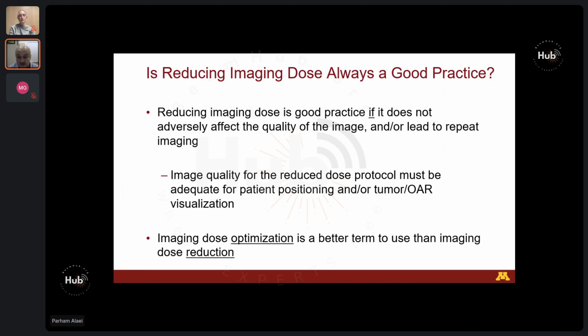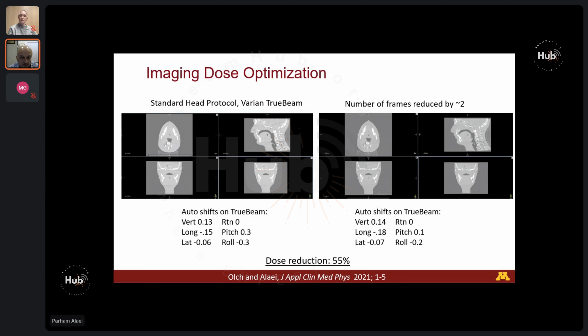We gradually reduced the frames per second, or the number of frames, or the mAs, maybe kV on the head and neck, and then we did the auto match feature on the TrueBeam in the LINAC. So we were just checking to make sure the auto match based on bony anatomy works with the lower dose protocol. Again, there is no soft tissue contrast in here, it's a phantom, so just a bone in there. And cutting the frames by 2, and the auto shifts that you click auto shift on the TrueBeam XI, it actually got virtually the same numbers. So again, the dose was reduced by more than 50%, but the auto shift works for bony anatomy matching.